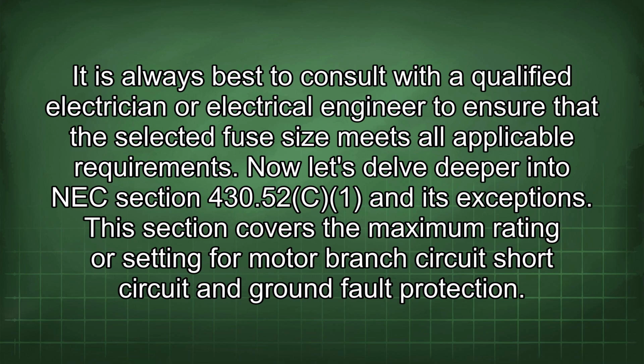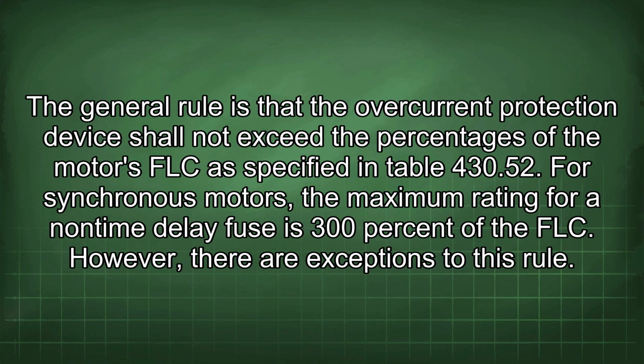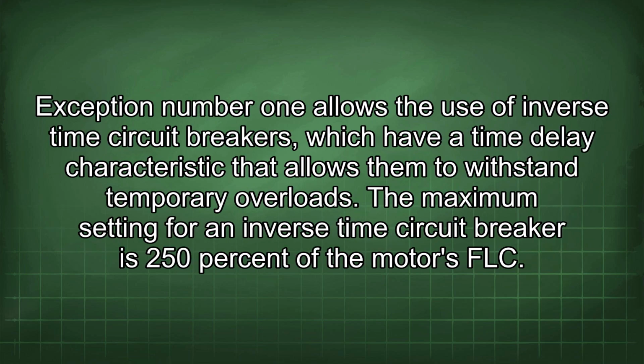This section covers the maximum rating or setting for motor branch circuit, short circuit, and ground fault protection. The general rule is that the overcurrent protection device shall not exceed the percentages of the motor's FLC as specified in table 430.52. For synchronous motors, the maximum rating for a non-time delay fuse is 300% of the FLC. However, there are exceptions to this rule. Exception number 1 allows the use of inverse time circuit breakers, which have a time delay characteristic that allows them to withstand temporary overloads. The maximum setting for an inverse time circuit breaker is 250% of the motor's FLC.